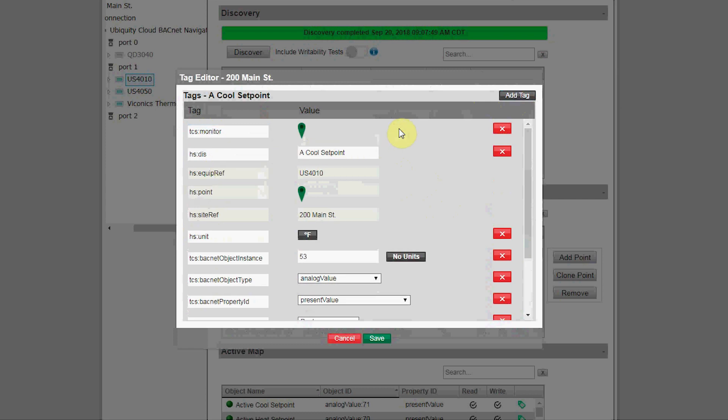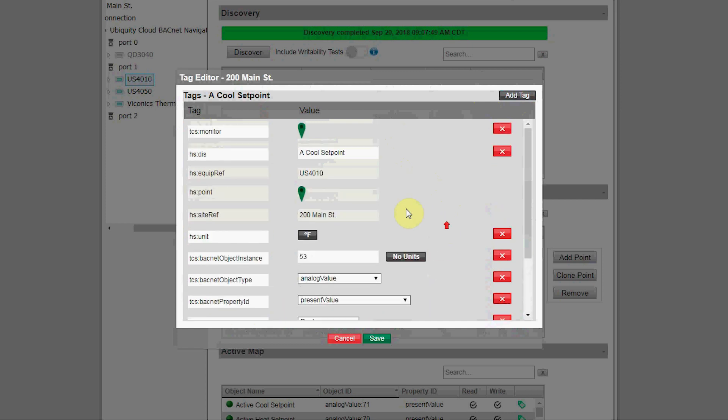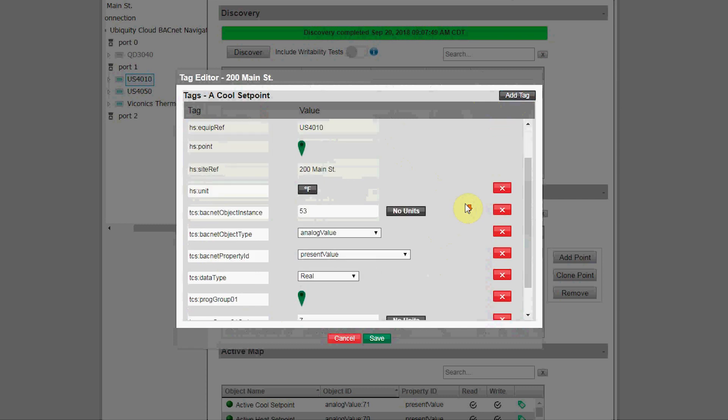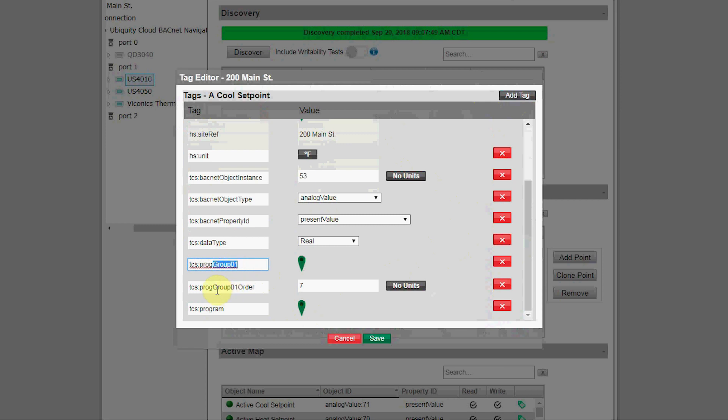To add a tag, click the Add Tag button and begin typing. In this case, we'll add a monitoring tag, so we type in 'monitor.' As you type, the list of available tags starts to narrow down the search. A library of tags will also be provided as a reference. You can add a monitor or program tag to make this object available for display on the monitoring page, which also trends the data to the Ubiquity database, or to be written to use on the programming page. You can add both tags if you want to both monitor and program that point.